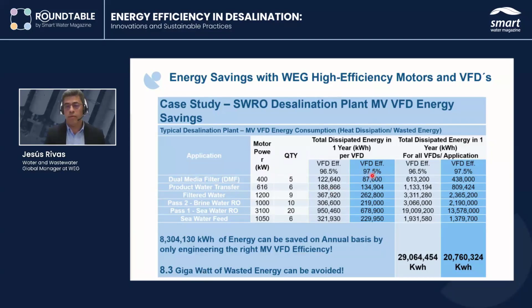So at the end, the final conclusion is, what are the benefits of improving the efficiency in the motors, in the main line or in the whole plant? That's clear. Cost savings and energy efficiency. We can reduce the energy consumption up to 30%. We have IE5 motors, high voltage motors made to measure, fit for purpose. In the same way, we are reducing the operational cost because we are reducing the electricity demand. At the same time, we are also using drives to optimize the process, to optimize the operating points, and we can automate the plant. So these energy savings are linked directly to the reduction of CO2 emissions. So the carbon footprint is much less in the desalination plant.